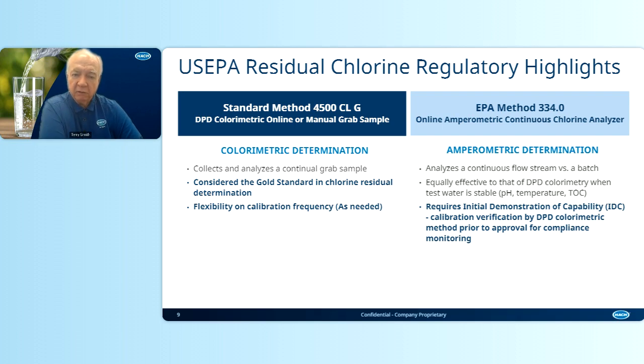EPA Method 334 is the online amperometric continuous chlorine analyzer. It analyzes continuous flow versus a batch. It does work well as long as the water is stable for pH, temperature, and TOC, but it requires an initial demonstration of capability. That means calibration verification with the DPD colorimetric method prior to approval for compliance monitoring. And this IDC is a little more complicated. It can take up to 14 days for you to complete.